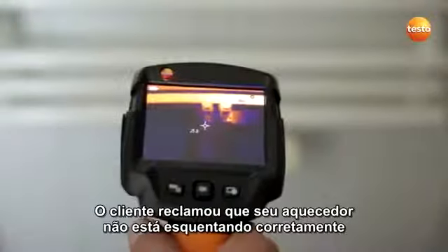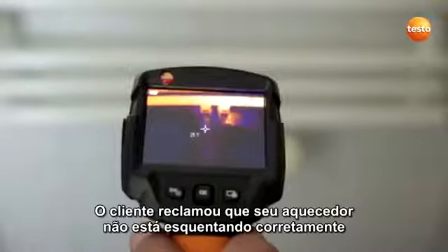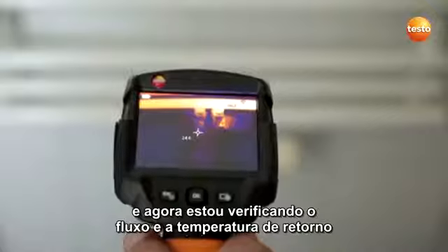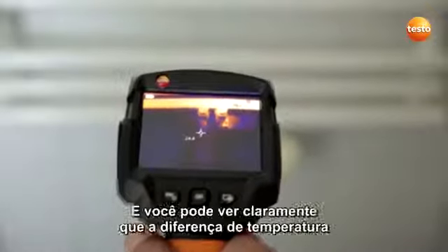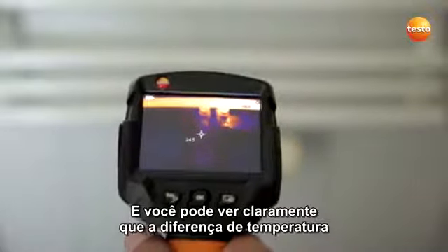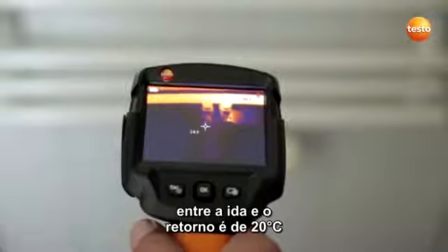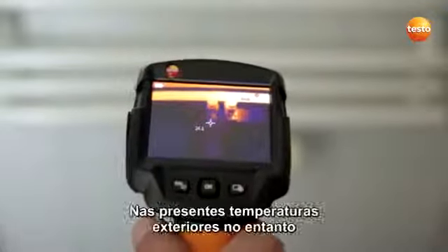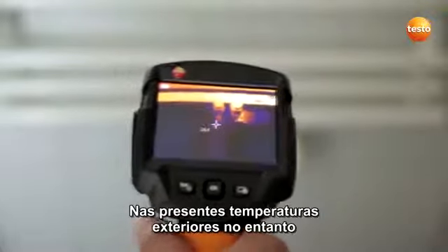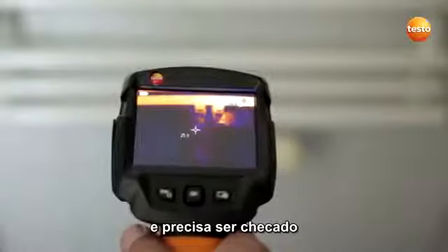The customer has complained that his radiator isn't heating through properly, and I'm now checking the flow and return temperature. And you can clearly see that the temperature difference between flow and return is 20 degrees Celsius. At the present outdoor temperatures, however, it shouldn't be more than 5 to 10 degrees. This means that the hydraulic balancing in the house is incorrect and needs to be looked at.